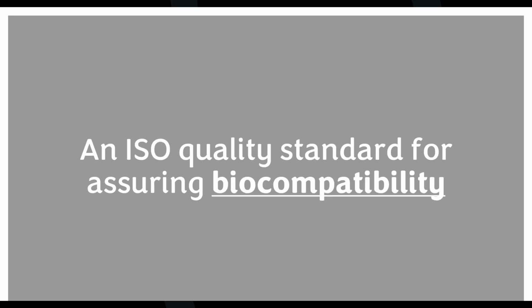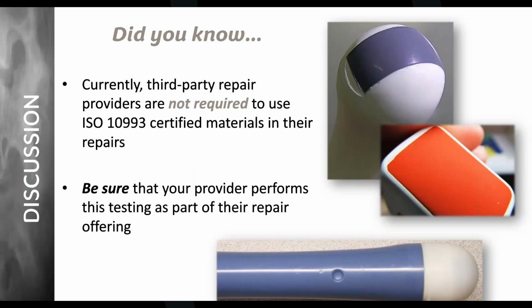Anyone know the ISO quality standard for biocompatibility? It's an ISO standard. Skip one, I went too fast. ISO 10993 is the biocompatibility standard, and it's something we do in our R&D lab in Denver to ensure that any of the materials we use in our repair process will not cause irritation or issues with the patient. Because we are a registered manufacturer, we follow most manufacturing guidelines, even in our repairs. Now, I can start up probe repair, coil repair in my garage tomorrow, and I can do that legally. Any of us can. Now, are you getting those probes or coils back to OEM form, fit, function, safety, and efficacy? Probably not. A lot of the things we do, we don't do because we have to, we do because it's the right way to do things.